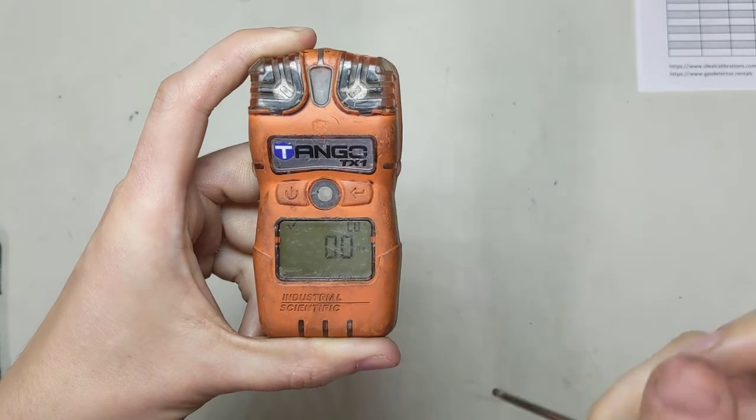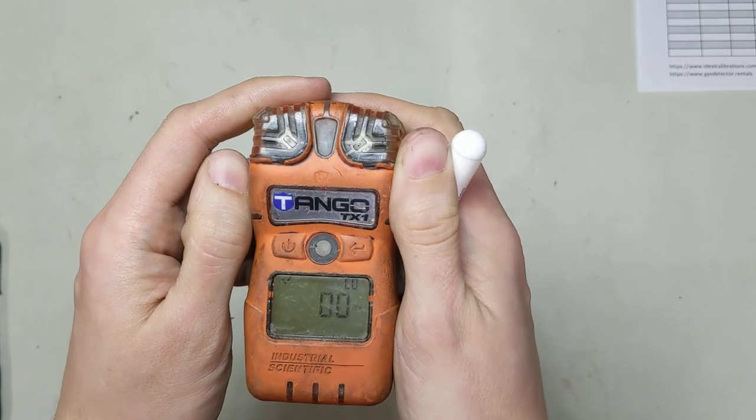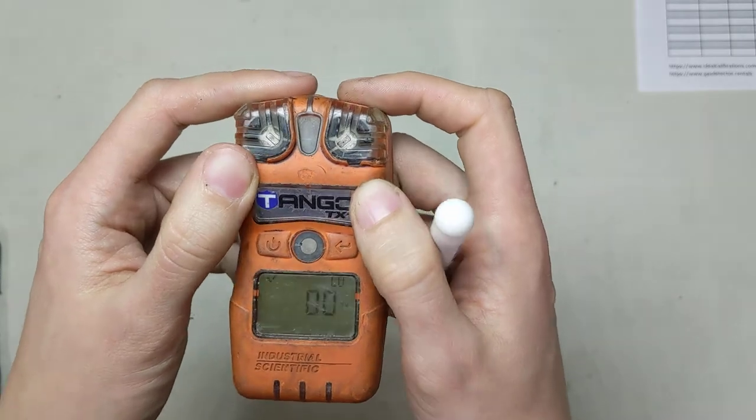But that's my recommendation. Do you ever get an SE1 or SE2? Just know that you might want to check those sensors and see if they're slotted properly before you send it out and spend a few hundred bucks on having someone like me just pop it back in there and recalibrate it for you.